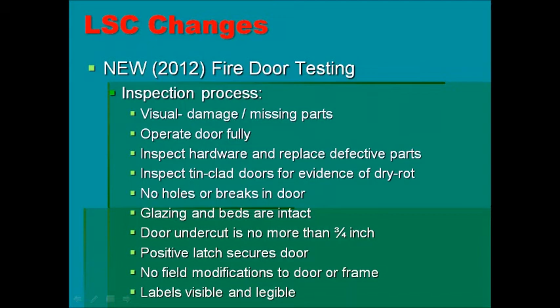You've got to do a comprehensive inspection of all the fire doors and smoke doors that are rated within your facility. Some of you probably have already had vendors show up at your door saying, we can do this for you. CMS says that your facility staff, your maintenance staff, can perform these functions in accordance with routine maintenance, but it has to be documented. And here's just a brief snapshot of all the things that you have to maintain and inspect on the annual FDAI. So make sure that you become familiar with this new requirement because it's really important to maintain the continuity of those doors.